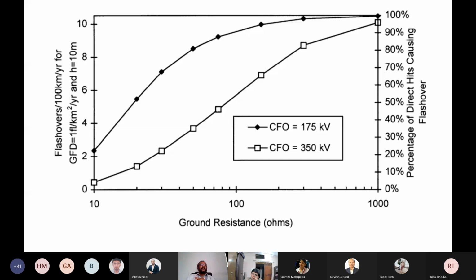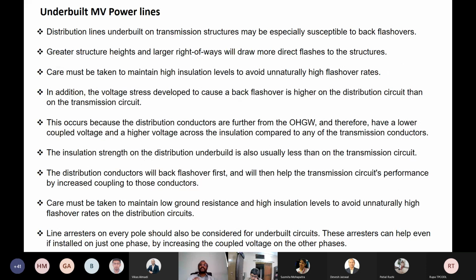Then underbuilt MV power lines. Distribution lines underbuilt on transmission structures may be especially susceptible to backflashovers. What do you mean by underbuilt MV power lines? You will find that even in India, I have seen in some parts of the country, there are HV lines and then MV lines are built underneath that. So if you have your substation connected to these underbuilt MV power lines, you have to pay a little more attention to that, because there are several points. Distribution lines underbuilt on transmission structures may be especially susceptible to backflashovers. Why?